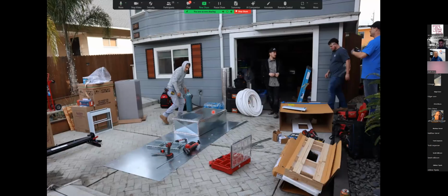The other benefit is these are MERV 13 filters, 4-inch media filters. If you stretch one out, it's got about 25 square feet of particle-trapping surface area, designed for 1600 CFM. Most of the time I'm putting these on systems under 800 CFM, so the filters are quite effective since I'm pulling air through more slowly. In a lot of the climate zones we work in, customers only need to change them once a year because they don't have a high cooling climate. In other parts near Sacramento, they change them twice a year.